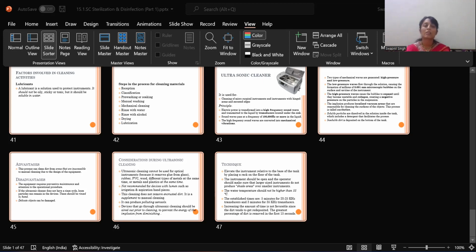Now, the sterilization cycle incorporated into an autoclave. Firstly, it begins with the warming of the chamber, then vacuum extraction takes place, followed by pre-steam penetration time, then steam penetration time, followed by holding time, and finally the cooling.